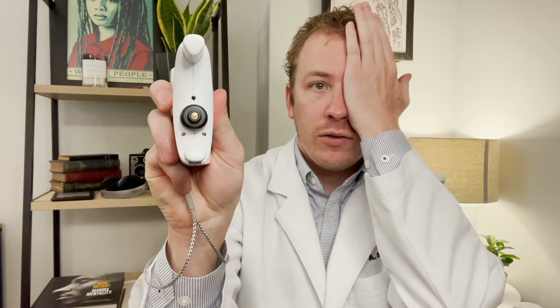I'm going to go all the way down towards that 8.5, which is what I measure myself. And then you can actually take individual measurements by clicking this, but I like to hold it down, and it'll take as many measurements as is necessary for it to determine that it's a quality measurement. So I just like to hold it down. So I'll cover the eye again, and I'll reset it because we had an error. And I'm going to place this on my forehead and my cheek, get it so I can see the full green circle. Hold it down. And 1 beep means it's done. Good capture. Done right there.